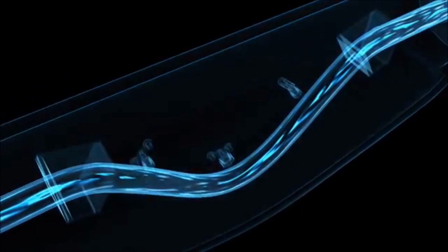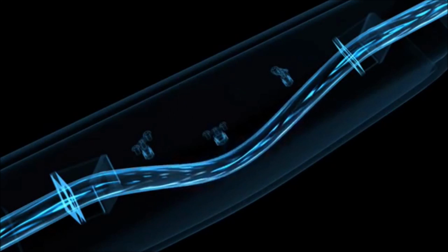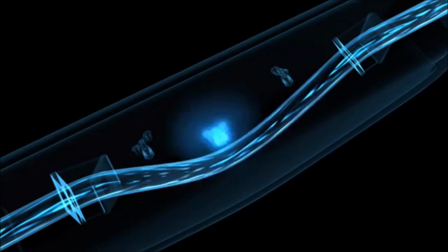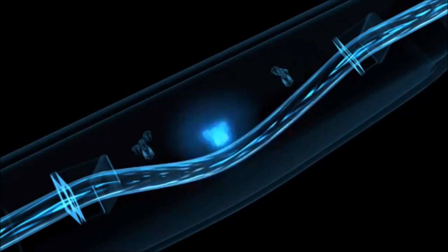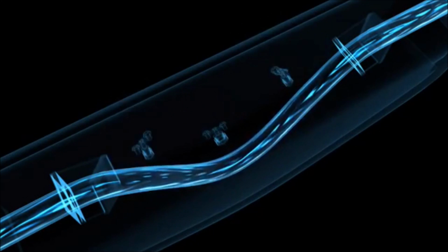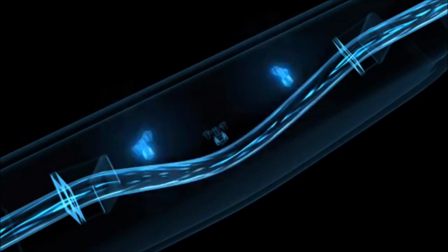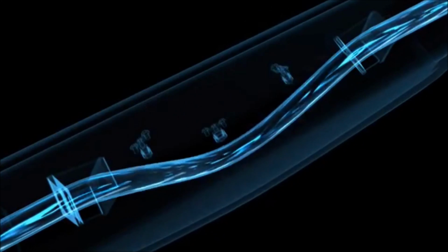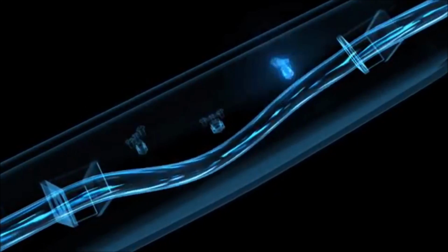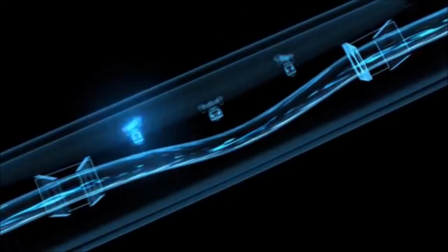An exciter causes this tube to oscillate constantly, here in an exaggerated example. If there is no flow, the measuring tube oscillates uniformly. Sensors are located at the inlet and outlet and register this basic oscillation precisely. As soon as the fluid starts to flow in the measuring tube, however, additional twisting is imposed on the oscillation as a result of the liquid's inertia.